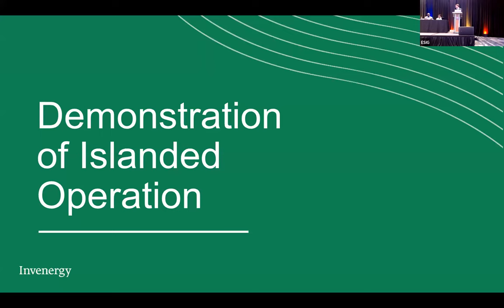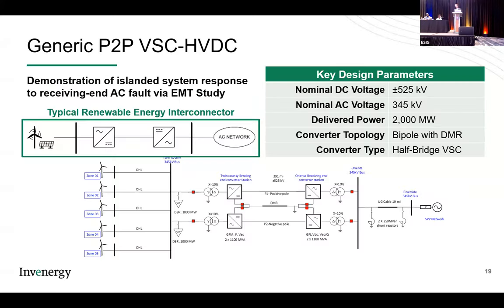Okay, so now we can touch really quickly thinking about maybe an example of how this islanded network piece could be done. So this is not going into the full multi-terminal AC side connection, but this is your traditional point-to-point islanded AC generation system connected radially to a load. And what we'll talk through is just some examples, one example of the performance of the HVDC. So we're going to look at that typical interconnector point to point, and we're going to see what happens when there's an AC network fault on the AC side or on the receiving end.